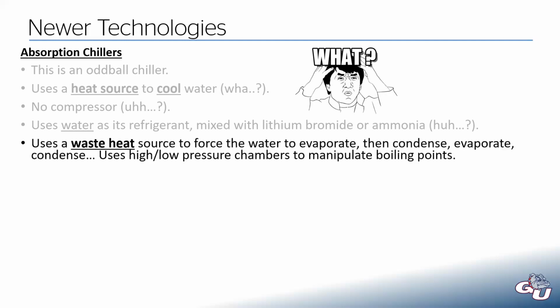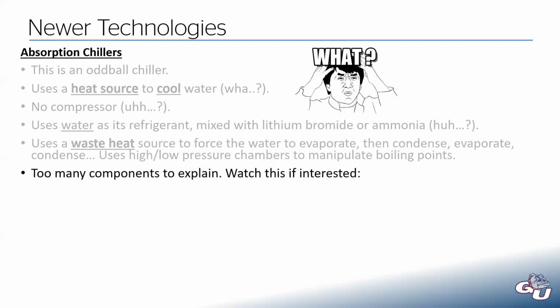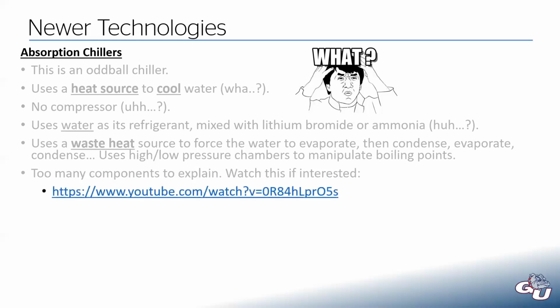It's using a waste heat source, which forces the water, which is our refrigerant in this case, to evaporate, and then it condenses, and evaporates and condenses. It does this through some high and low pressure chambers that manipulate the water's boiling points. So it is still a refrigerant process, going between a high pressure gas and a liquid back and forth, just like other refrigerant processes in air conditioning. But it's using these pressure chambers to manipulate the boiling points of the water, which normally wouldn't want to do these phase changes. There's way too much here to go over and explain. If you're really interested, there's a YouTube video on it.